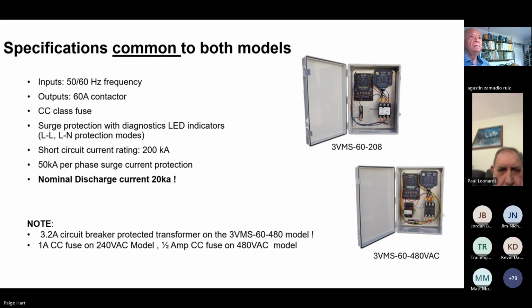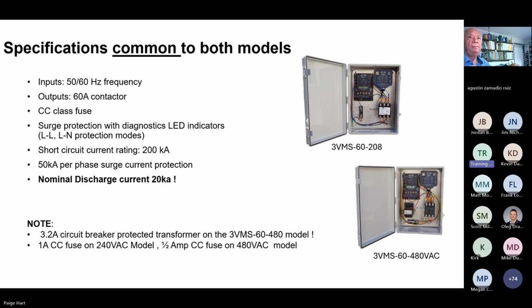Thank you. All right, so they all carry the same CC class fuse. They all have surge protection with diagnostic LED indicators for line to line and line to neutral protection modes. They both have short circuit current ratings of up to 200 kiloamps. They also both will protect up to 50,000 amps per phase. And they have a nominal discharge current of 20 kA.